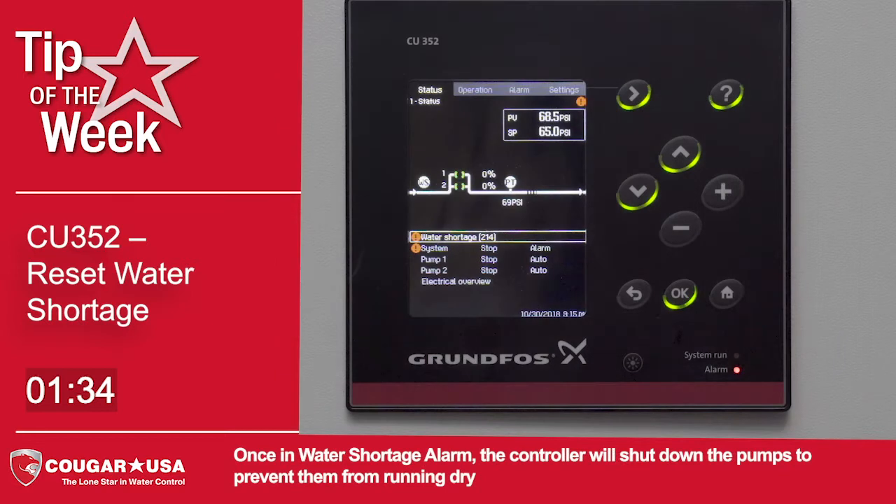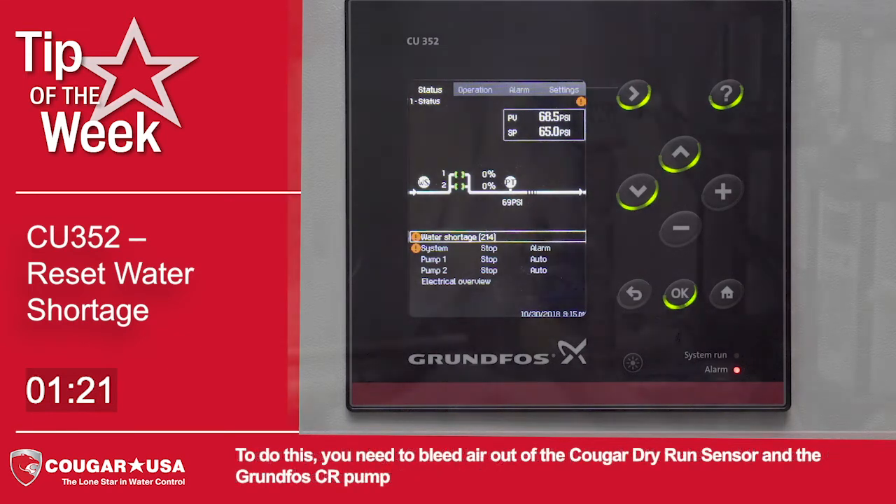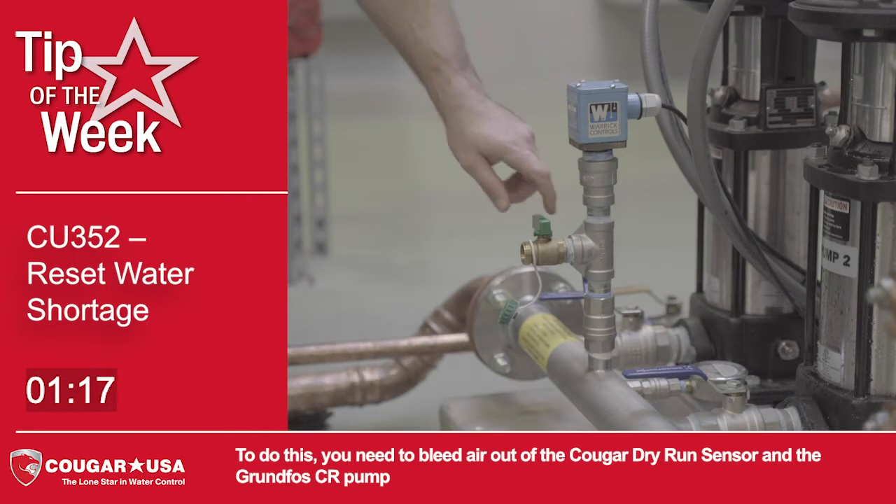Once in water shortage alarm, the controller will shut down the pumps to prevent them from running dry. The pumps will stay off until the system is primed with water and the alarm is manually cleared on the controller. To do this, you will need to bleed air out of the Cougar Dry Run Sensor and the Grundfos CR pump.